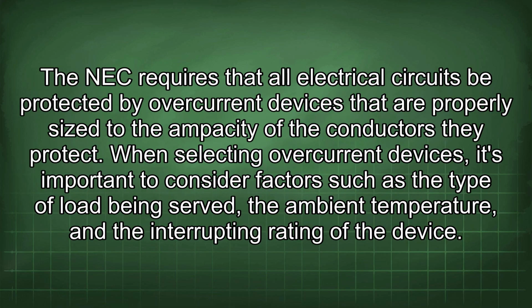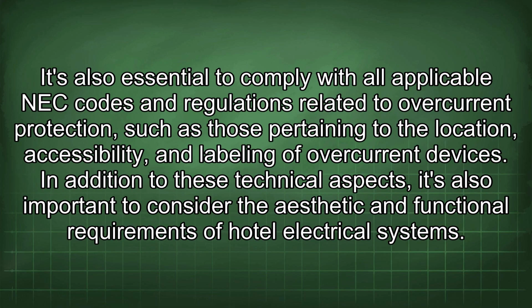The NEC requires that all electrical circuits be protected by overcurrent devices that are properly sized to the ampacity of the conductors they protect. When selecting overcurrent devices, it's important to consider factors such as the type of load being served, the ambient temperature, and the interrupting rating of the device. It's also essential to comply with all applicable NEC codes and regulations related to overcurrent protection, such as those pertaining to the location, accessibility, and labeling of overcurrent devices.